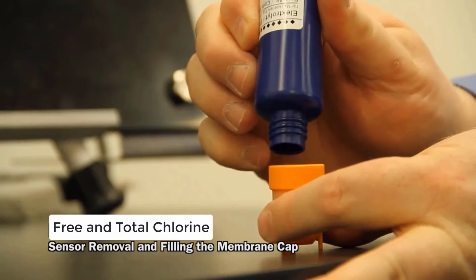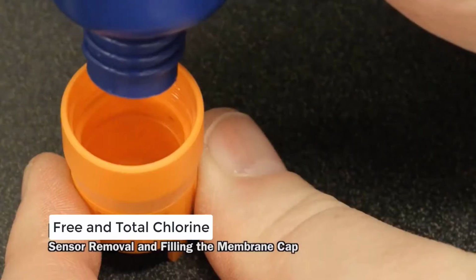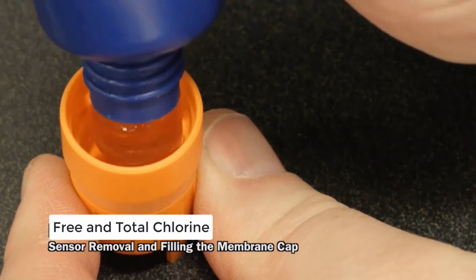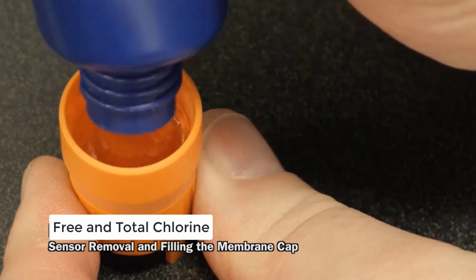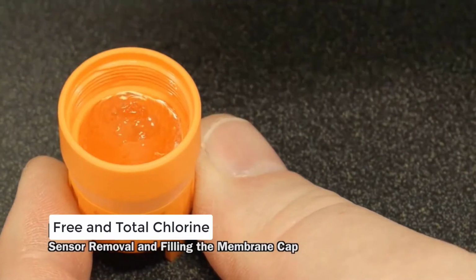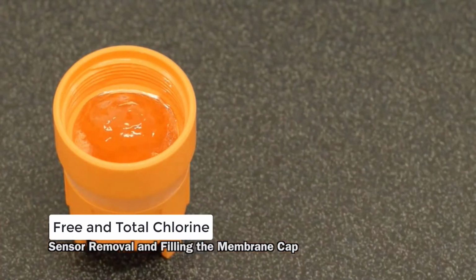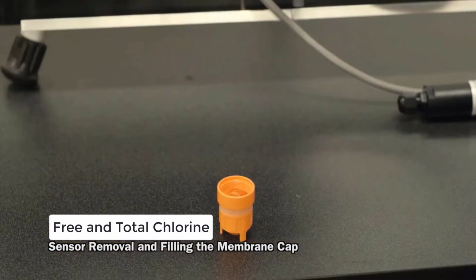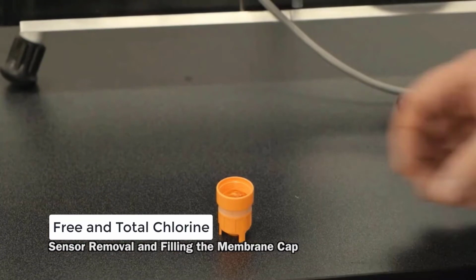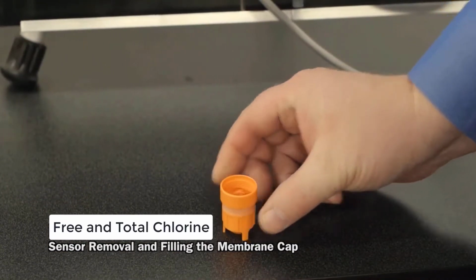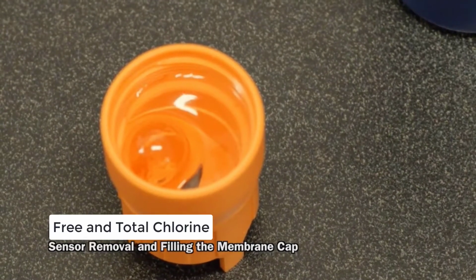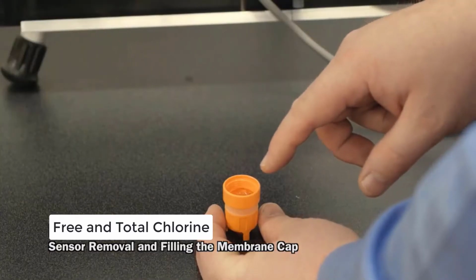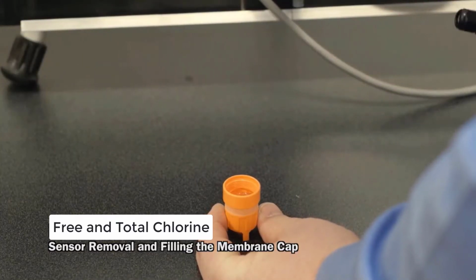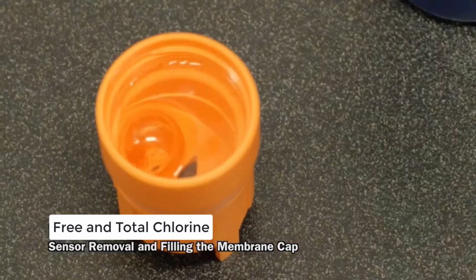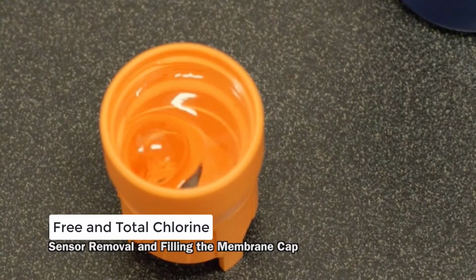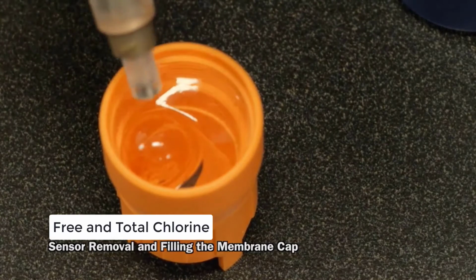We're going to fill that cap with electrolyte. Here you can see how much thicker the electrolyte is. We want to fill it again so there's no air bubbles. If there is an air bubble, that air bubble will migrate towards the top in time. We'll let that come to the top. Never put a screwdriver or any other instrument into the electrolyte. If you want to try to help remove the air bubble, use the sensor tip itself.